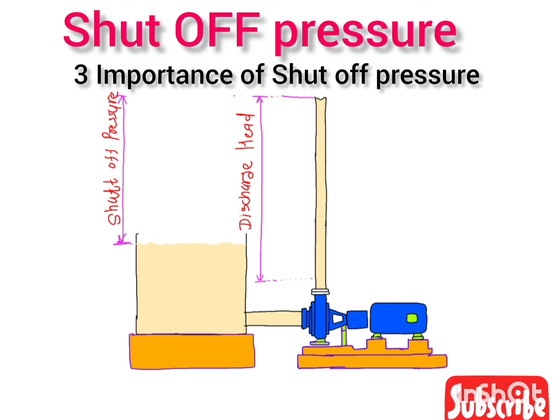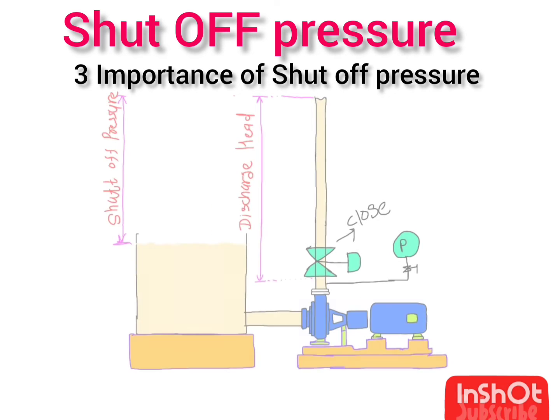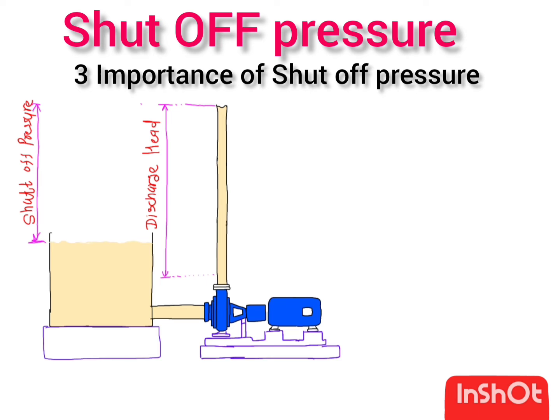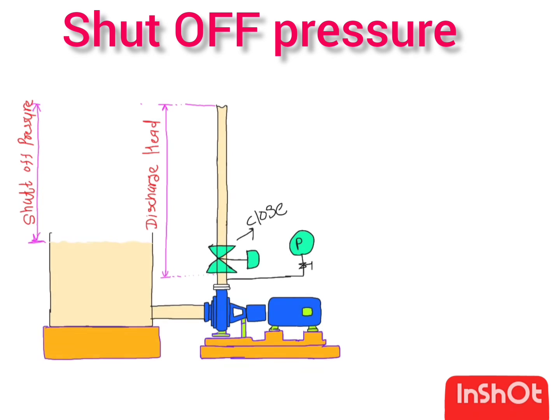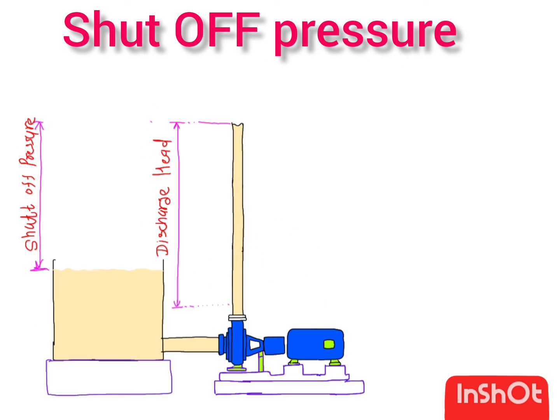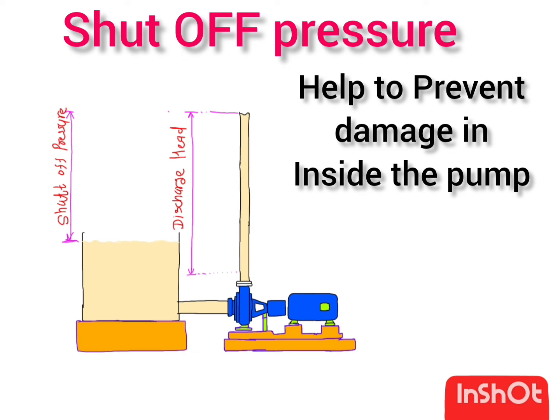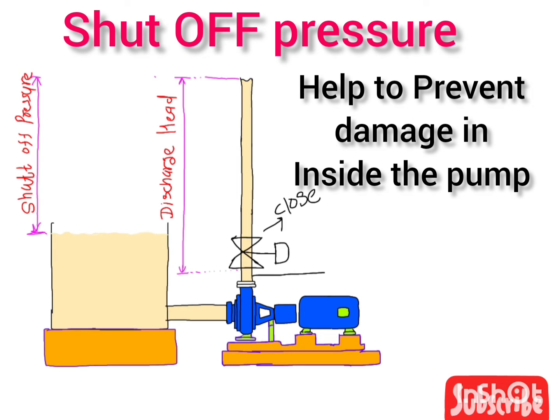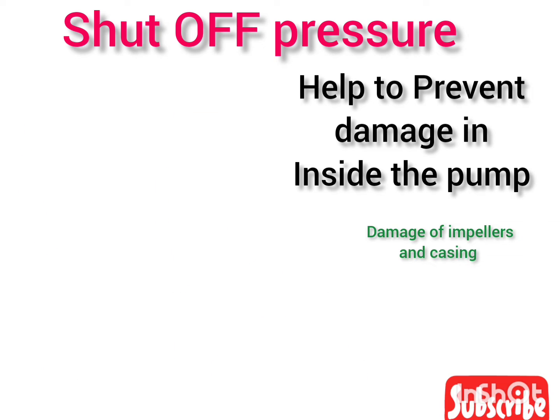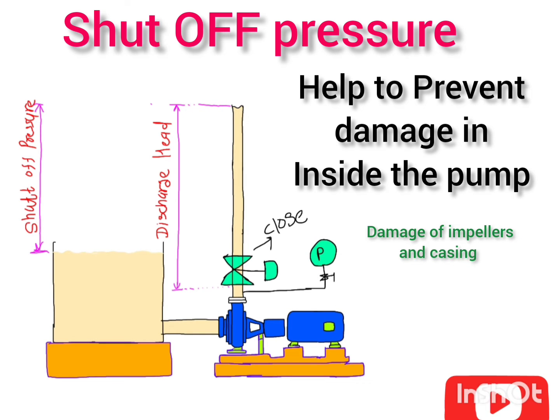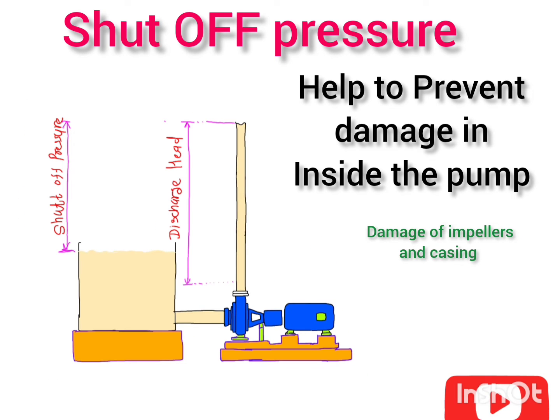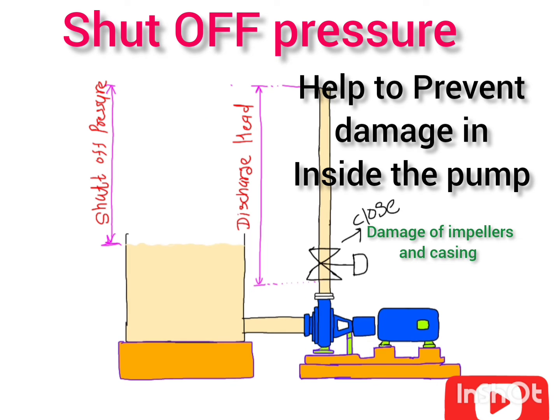Knowing the shut-off pressure gives three main benefits. The first benefit is that it helps prevent damage to the pump. If you close the valve suddenly, pressure increases and may damage inside components like the impeller and casing. Knowing the shut-off pressure helps you design the system to avoid this damage.